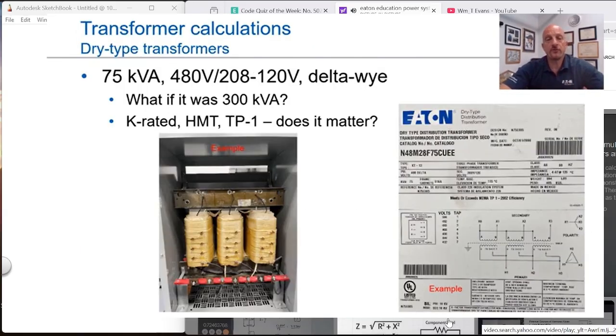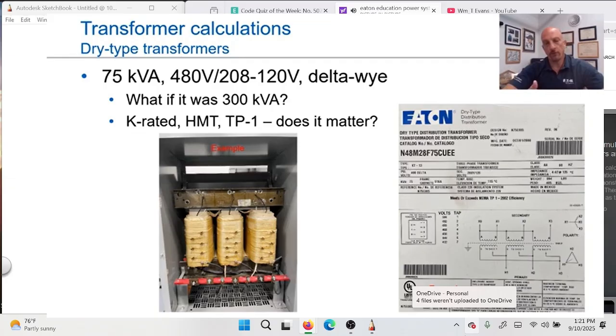Okay, so I showed you a few transformers earlier. Let's start to do some of those calculations that we talked about. Again, we're going to look for primary and secondary full load amps and secondary fault current. Here's the transformer, here's the inside of it, and typically you're not going to get to see it with the cover off. So what we usually do is we walk up to the nameplate and gather the information on it. What are we looking for? kVA rating, primary voltage, secondary voltage. Sometimes we worry about the configuration, if it's delta-Y or delta-delta, for example, but for these calculations it doesn't matter. And then we also look for impedance, the Z value that's on the transformer.